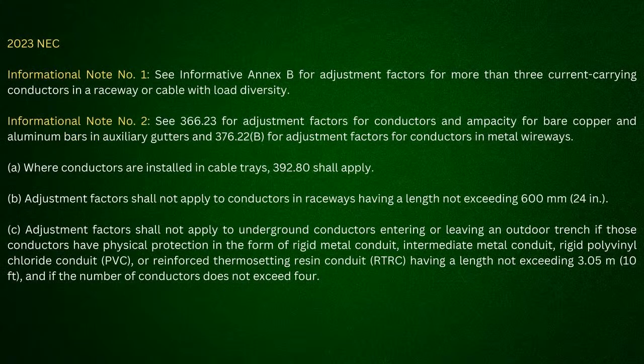And that's why I have problems with it. But anyway, then it gets in, and here's another one, and some of y'all that watch our podcast continuously or have gone through and watched some of the videos, informational note number 1 talks about looking at your informative Annex B for adjustment factors where you have more than 3 current carrying conductors where you could be in a raceway or cable, but you have load diversity.